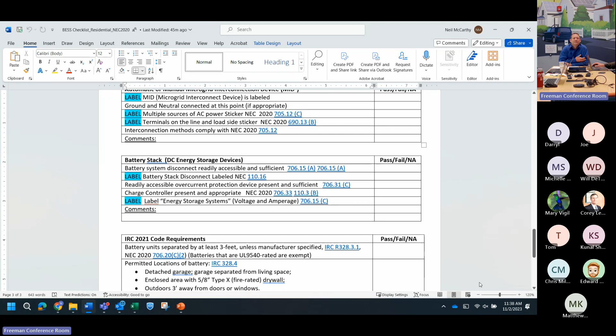So under the IRC code, if you have a 9540 rated box, you do not need to be 3 feet apart. Most of the newer boxes coming out are 9540 rated, and it should say so on the tag. I think all the batteries in our program are UL 9540, so this shouldn't really be a problem. This is more for informational purposes if anyone wants to check. But that hasn't always been true, this is true for about the last 2 years. So there could be equipment your distributor gives you, wanting to sell it and clear their warehouse, that could be 3 years old. If that's the case, check your tags.